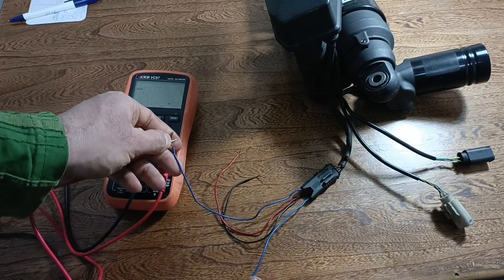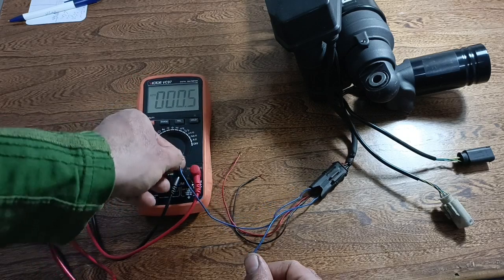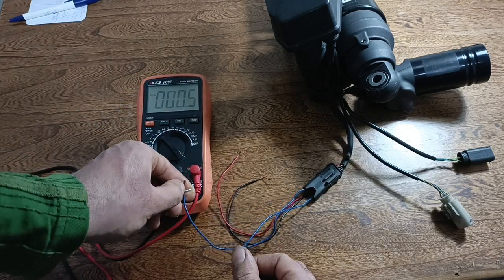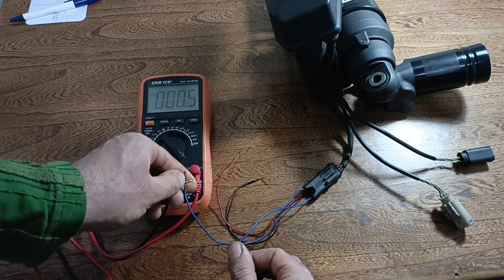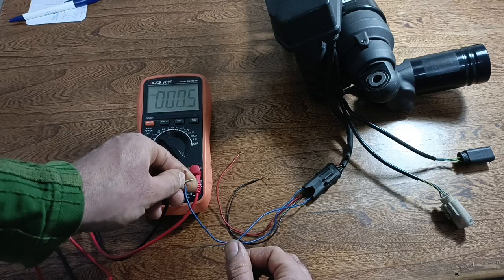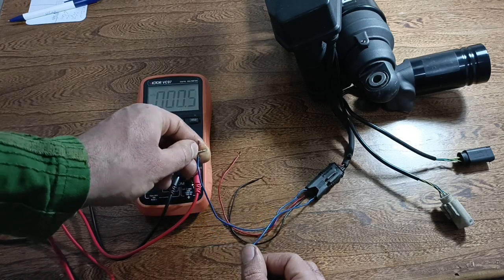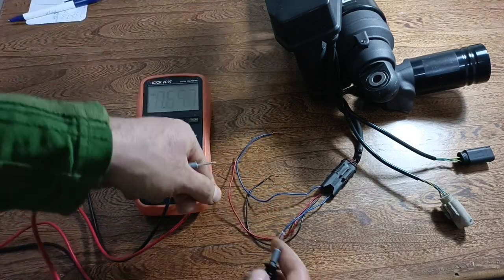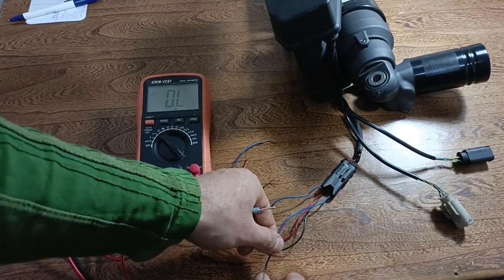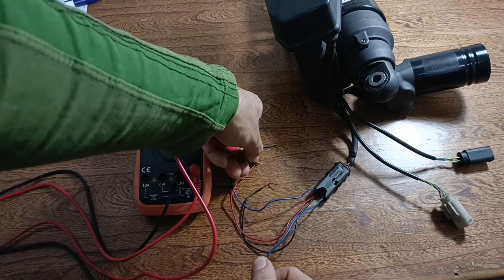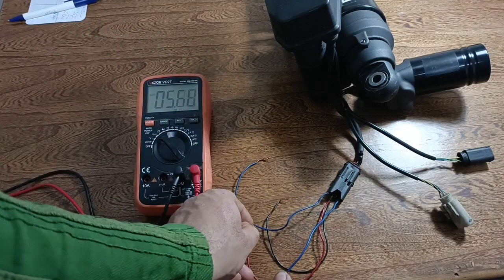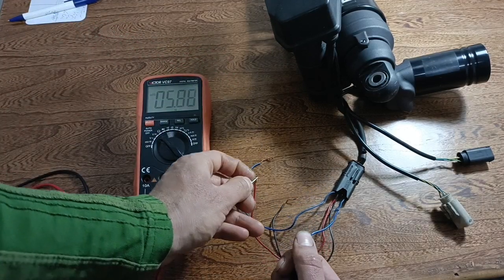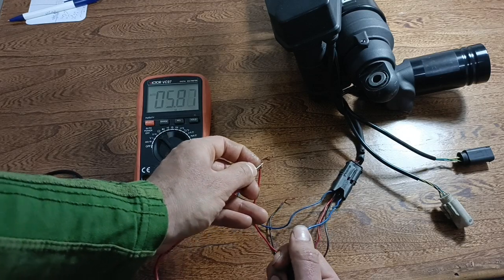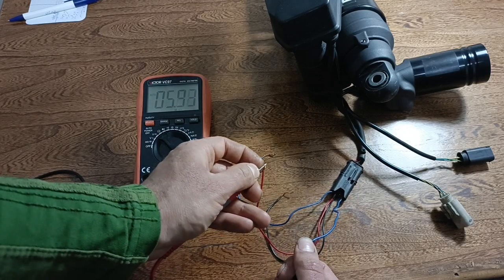The 2 side wires show a resistance of about 0.5, and between the 2 Hall effect sensor wires and the DC motor wires, we have 5 mega ohm, meaning there is no continuity with each other.